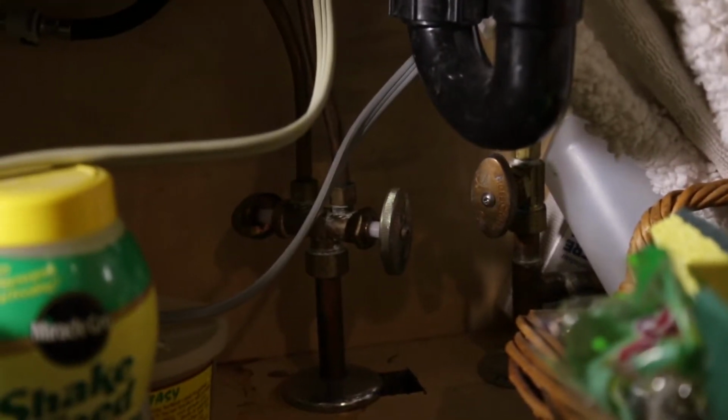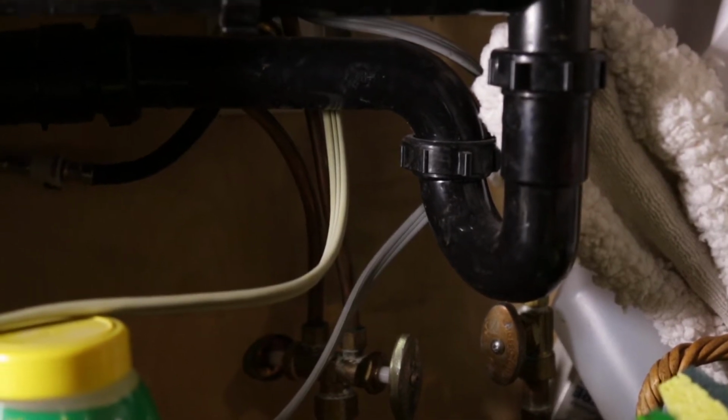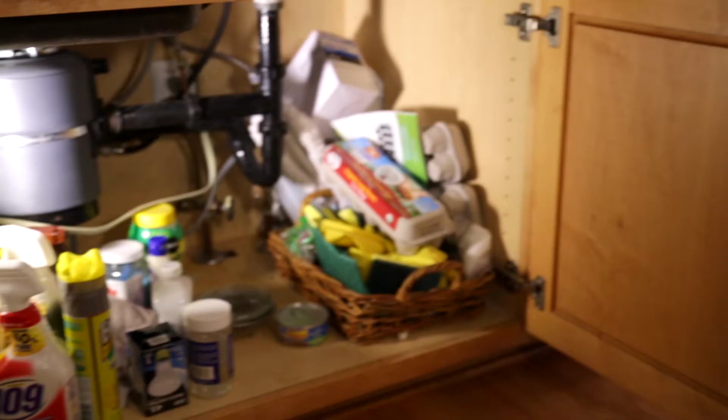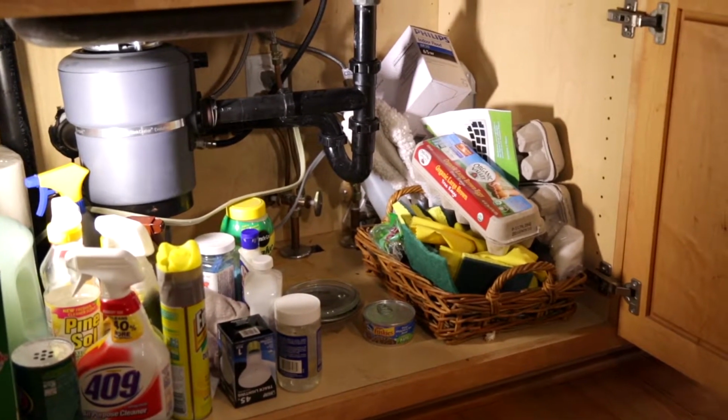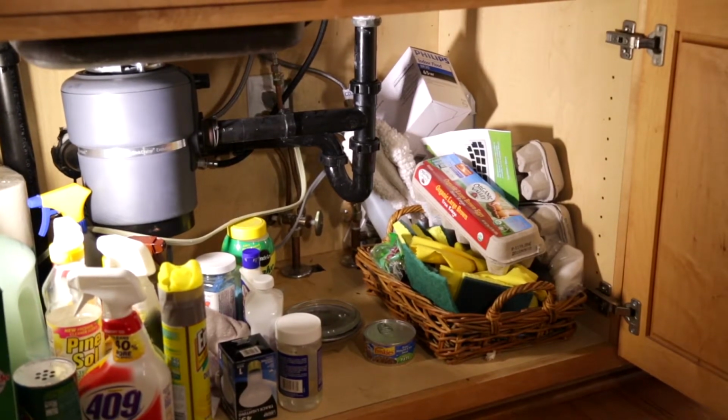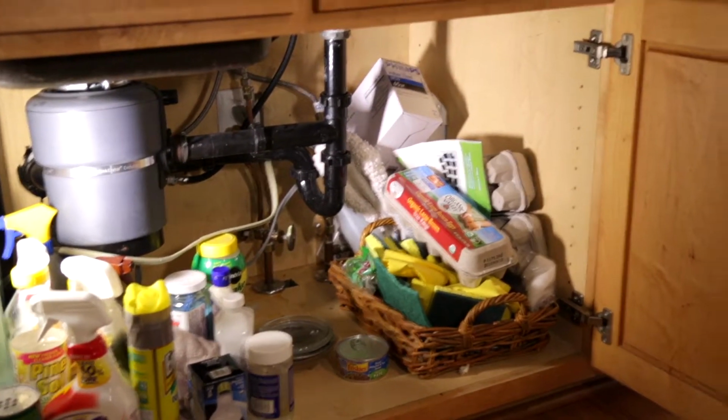We've tracked our errant current flow on the plumbing system up into the kitchen, following the water supply pipe for the refrigerator. We discovered when we got up here that the refrigerator is encased in cabinetry and would have to be pulled out to be able to trace the flow from the ice maker water connection through the power supply to the refrigerator. And we're not going to do that for fear of scratching up the floors. But we did find that part of the current has come over to the kitchen cabinet and to the garbage disposal and the dishwasher. So you recall my telling you that current flow on the grounding system takes all available paths back to the power company, and it wouldn't just stop with the refrigerator if there was another good path to take back to the power company.